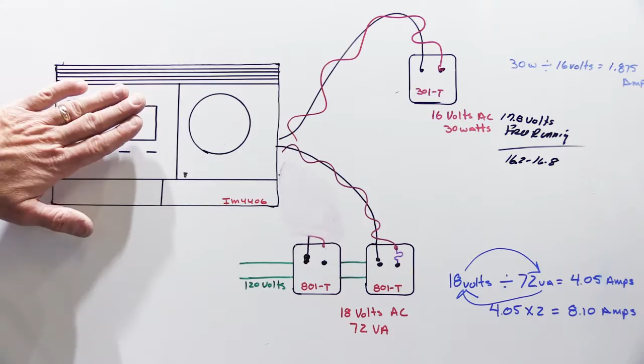So if you have it set up like this and you turn the power back on, so this transformer temporarily and the other 801T are both powering the master station, and you measure the voltage here, and it's somewhere in this range, 16.2 to 16.8, and the master station works properly, it's pretty likely that you don't have a serious fault or failure with your master station.